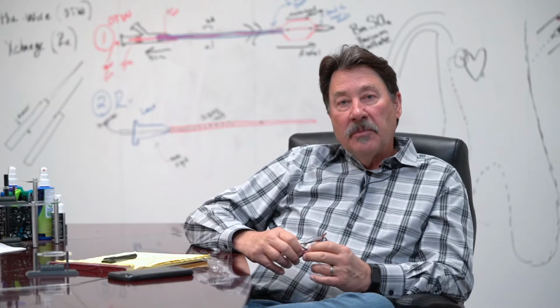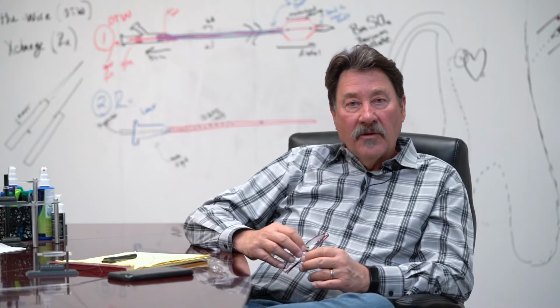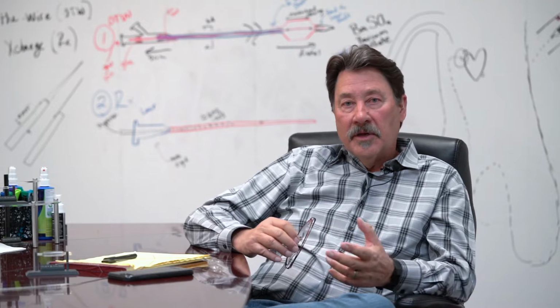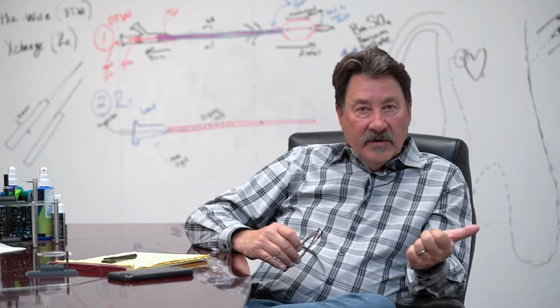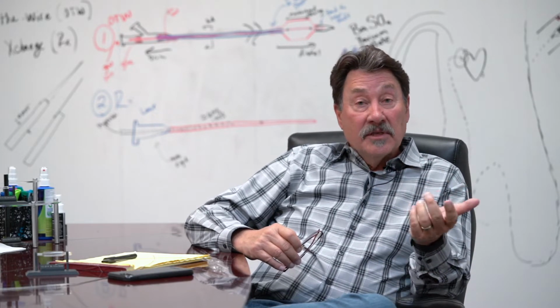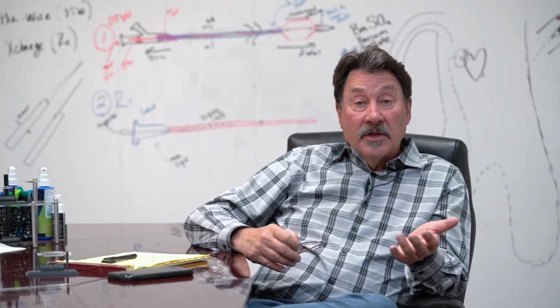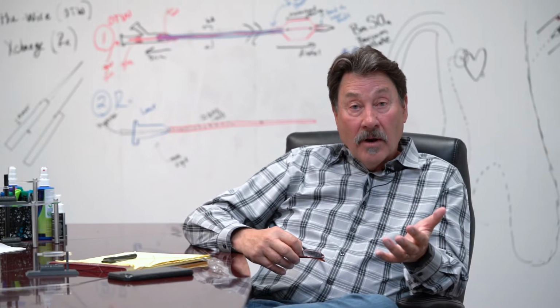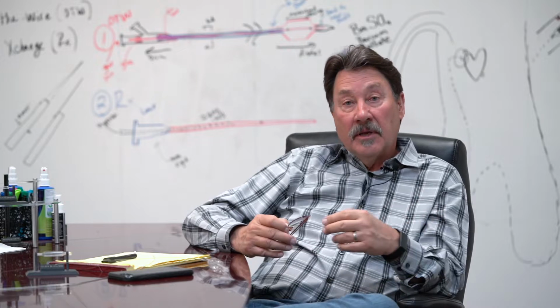So we'll often spend quite a bit of time delving into what are the design inputs, talking to the clinician about what does it need to have to function. And sometimes it can be some silly things like what color does the catheter have to be? Because sometimes in a background environment in the cath lab, the color becomes important.